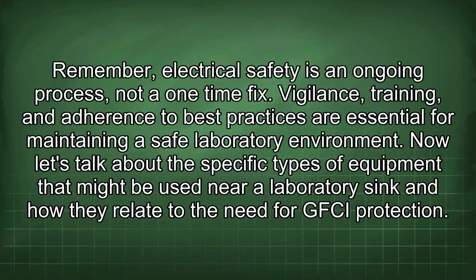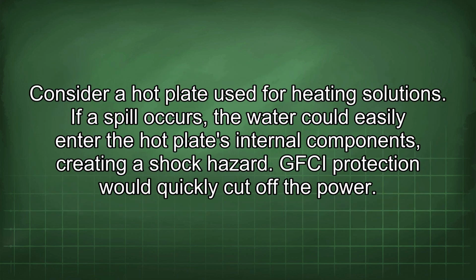Now let's talk about the specific types of equipment that might be used near a laboratory sink and how they relate to the need for GFCI protection. Consider a hot plate used for heating solutions. If a spill occurs, the water could easily enter the hot plate's internal components, creating a shock hazard. GFCI protection would quickly cut off the power.